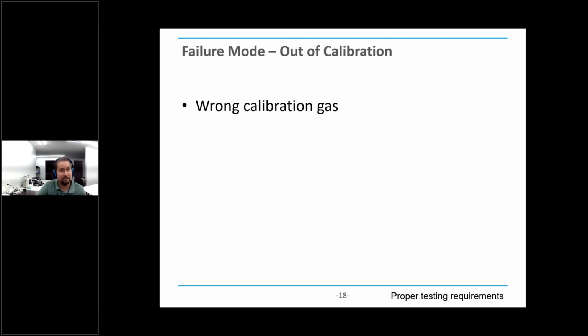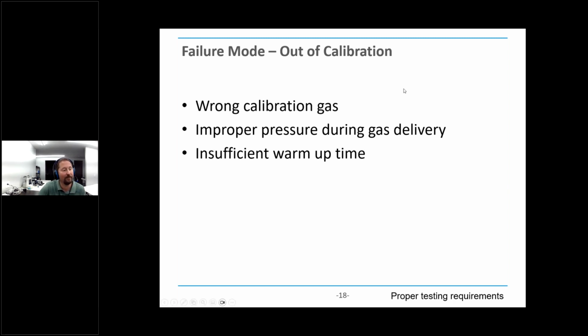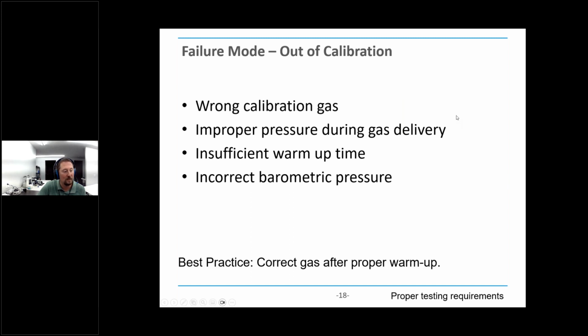Sometimes that's by accident, sometimes that's by choice. We've seen people deliver that gas incorrectly to the gas monitor. You're supposed to have a collection of bags and tubes and different things to get the gas out of the bottle to room pressure so that you can then draw that sample into the device. But if you're forcing it in, it can actually mess up your calibration. A lot of people don't wait long enough to calibrate them. And again, they use the wrong barometric pressure. So all of that stuff is things you should avoid in order to get a good calibration.